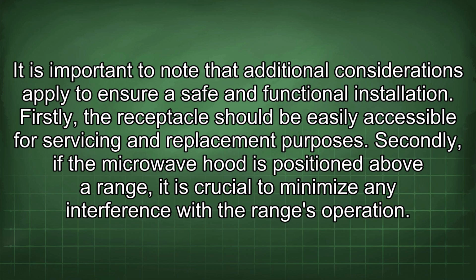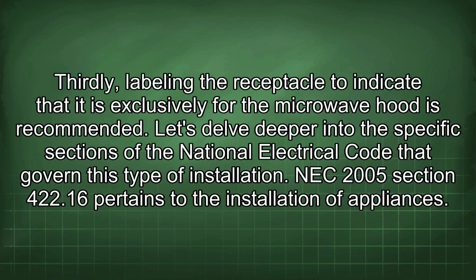It is important to note that additional considerations apply to ensure a safe and functional installation. Firstly, the receptacle should be easily accessible for servicing and replacement purposes. Secondly, if the microwave hood is positioned above a range, it is crucial to minimize any interference with the range's operation. Thirdly, labeling the receptacle to indicate that it is exclusively for the microwave hood is recommended.